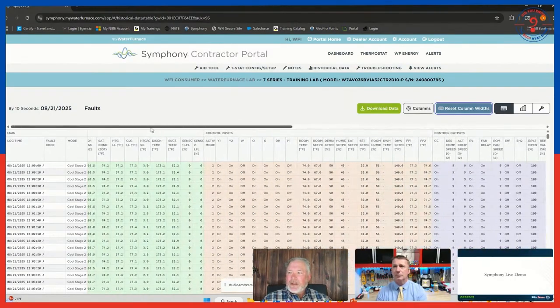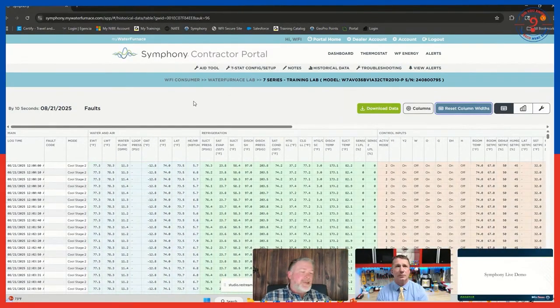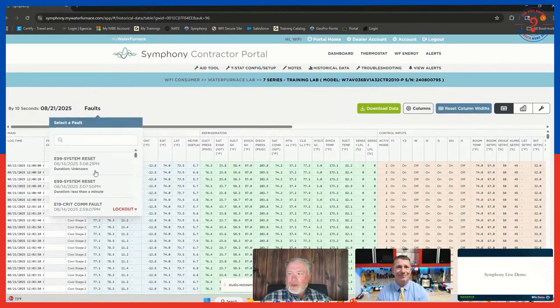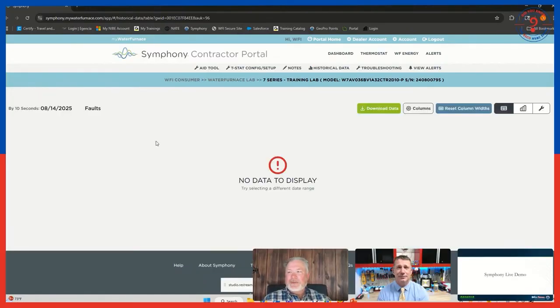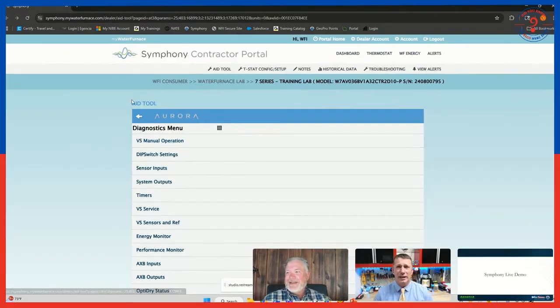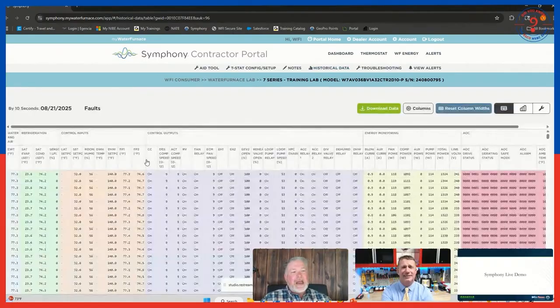The neat thing about this is, let's say a customer called in and said, hey, my unit locked out the other night, I reset it, everything's fine now, but I don't know what happened. All I have to do is go here to faults, and it'll pull up whatever my last fault was. Like here you see lockout. And this was that E19 critical communication error. If I click on that, it'll take a second, but it'll load back up here. Whoops, maybe not. Okay, what kid ran down the hallway and knocked the thermostat off? Something happened there. But it'll actually take me to the date and time that happened.